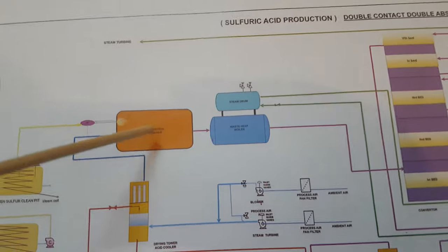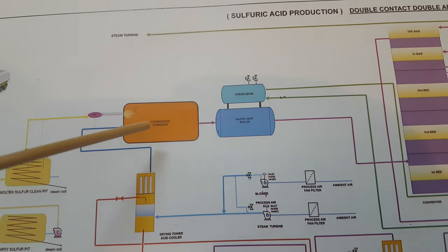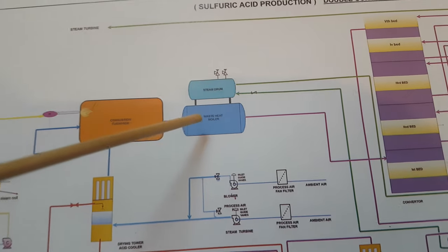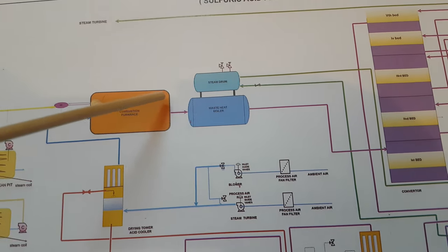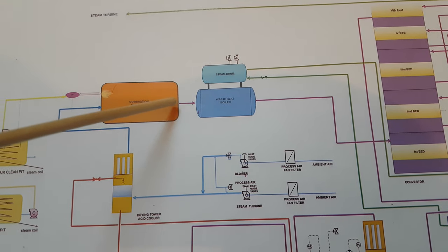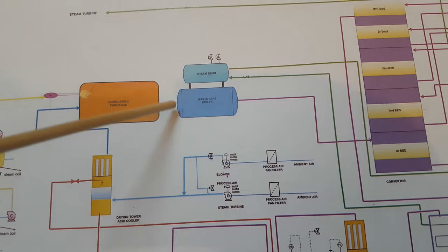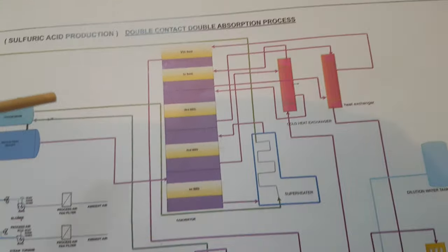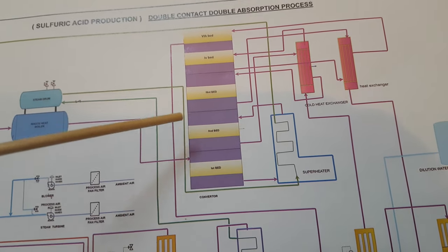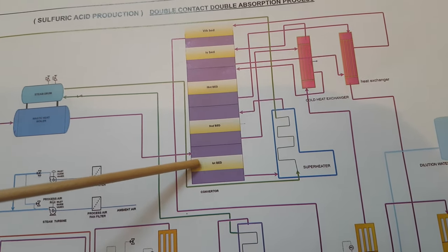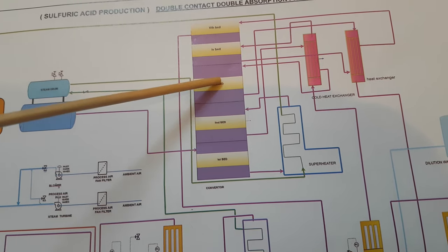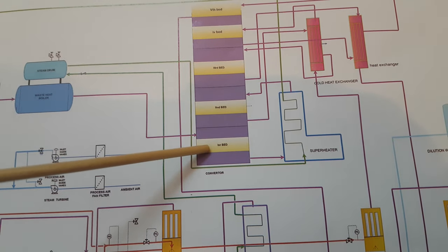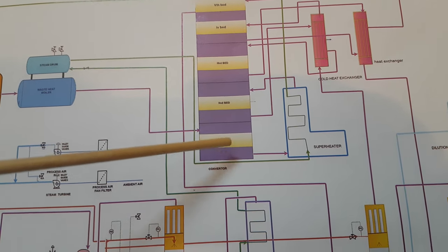After that we have the combustion furnace, where combustion takes place. Sulfur reacts with oxygen and turns to sulfur dioxide. This is the waste heat boiler — the furnace temperature is around 1000°C, so we have to remove that heat from the process gas. The waste heat boiler removes the heat and generates steam. This is the catalytic converter, which has five beds — one, two, three, four, five — or you can pick three or four beds as per your acid production requirement. The beds have V₂O₅, vanadium pentoxide catalyst.